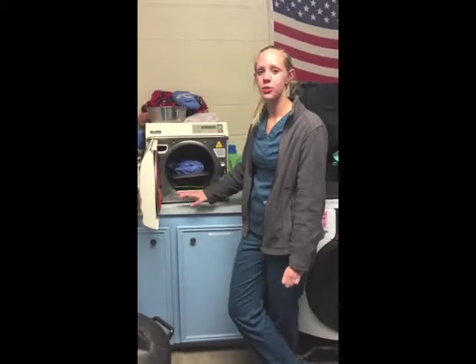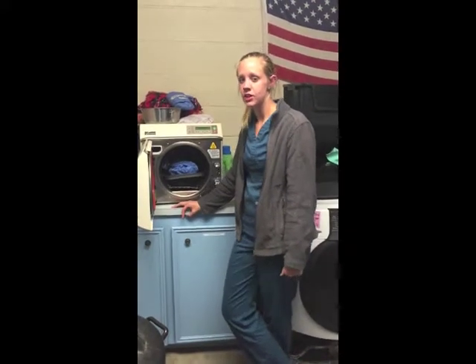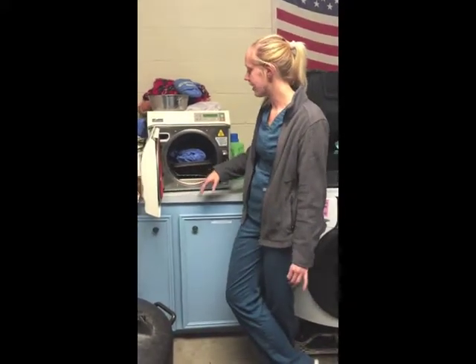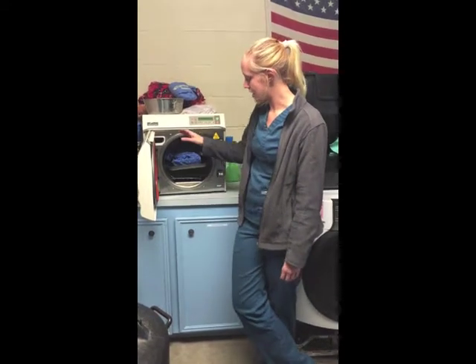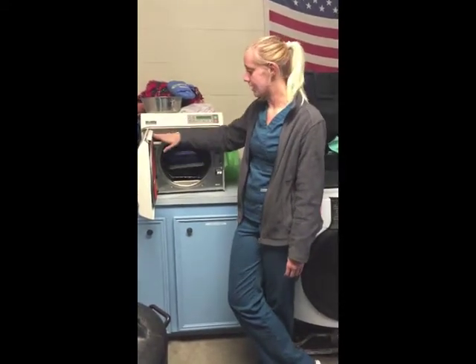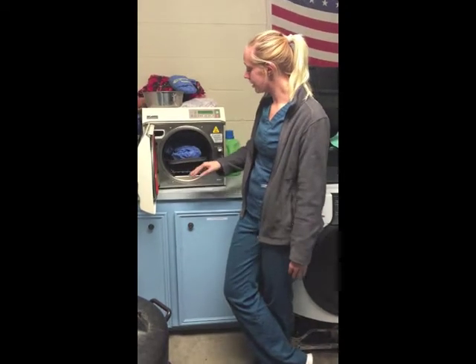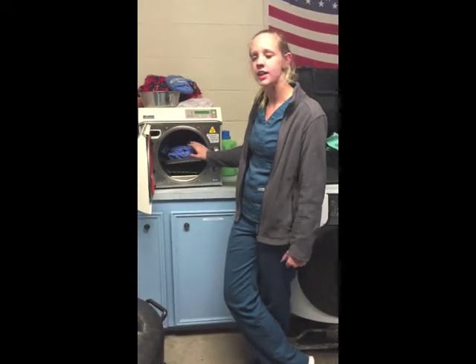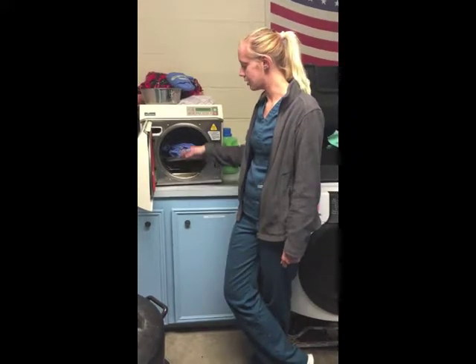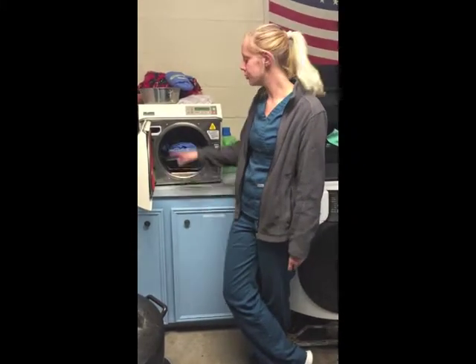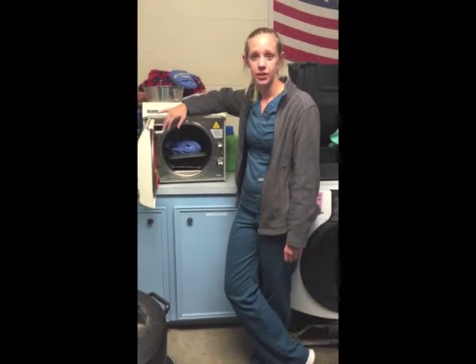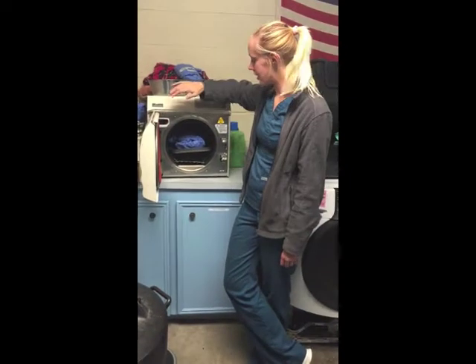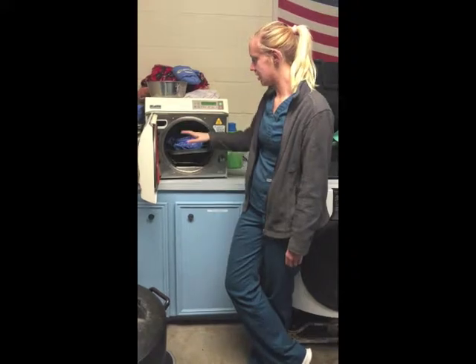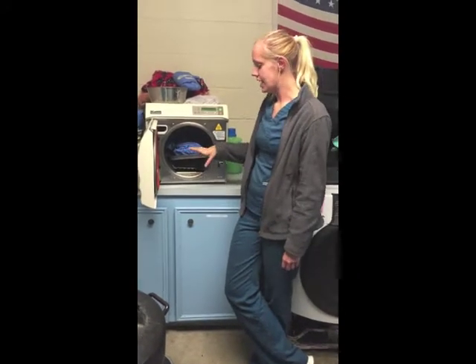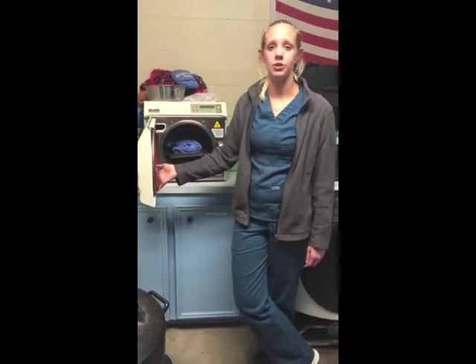So some autoclaves require a weekly and a monthly maintenance. So the weekly would just be kind of cleaning it out and rinsing it out and wiping it and emptying it and filling it back up with distilled water. And then the monthly, that would be your more heavy duty cleaning. And that is where you empty the whole chamber, empty all the water, put whole new water in, and run a cleaning agent through it, so that you can clean out any excess water, any excess debris that has built up within, and making sure that the valves are secure so there's no leaking within the autoclave itself.